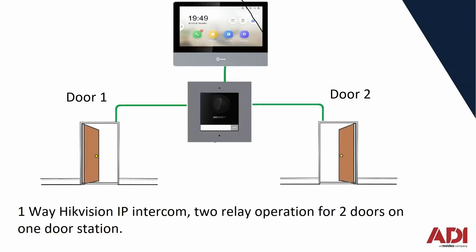The system is already set up in IVMS and it's a working system. All we're going to do now is enable relay 1 and relay 2, so when you receive a call on your handset you can select one or two. For example, an application where you have a vehicle gate and adjacent to it a pedestrian gate — you can select which gate you're going to open.